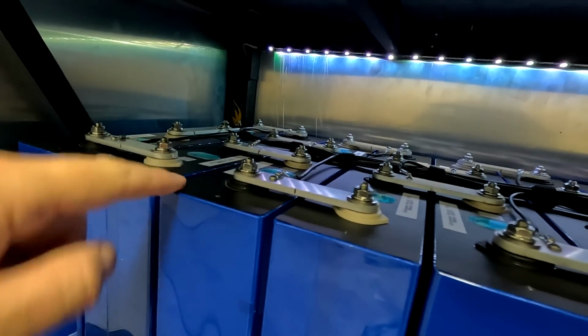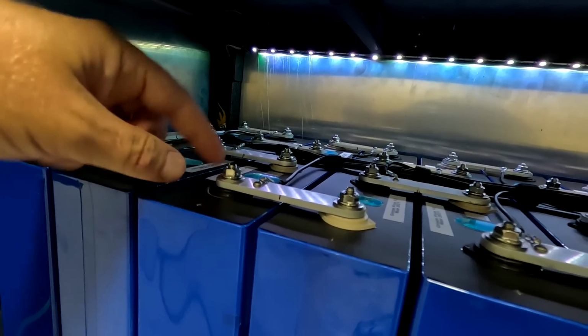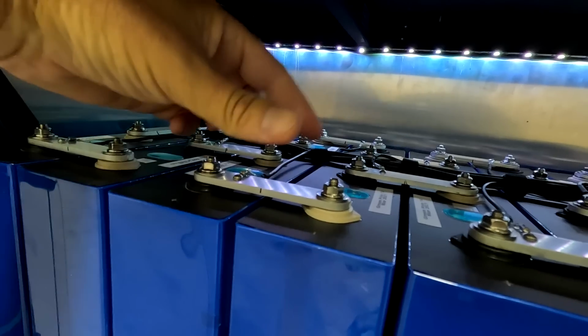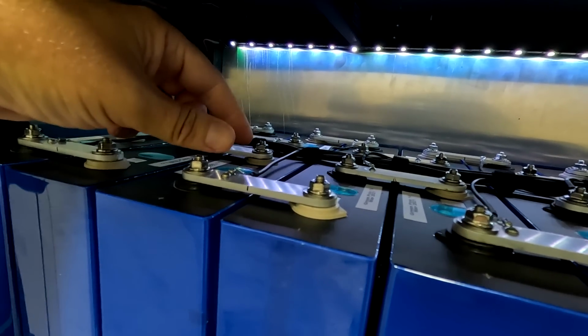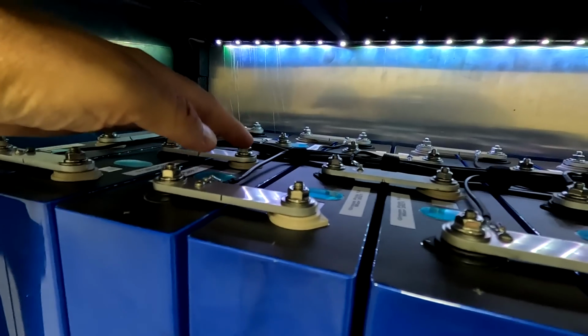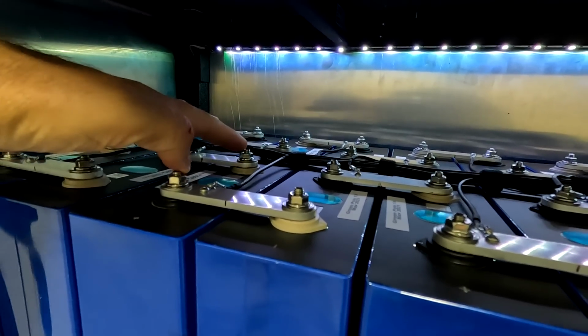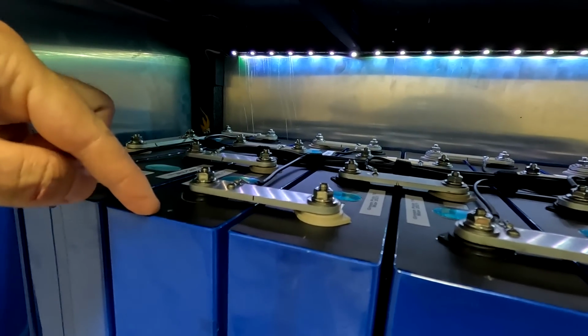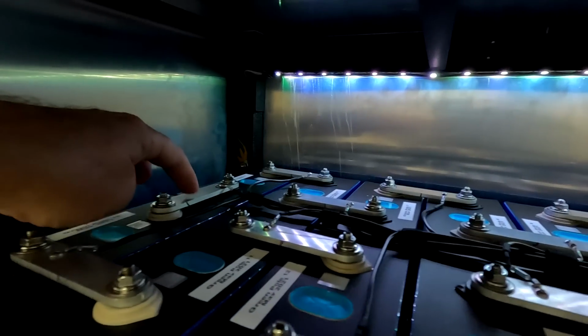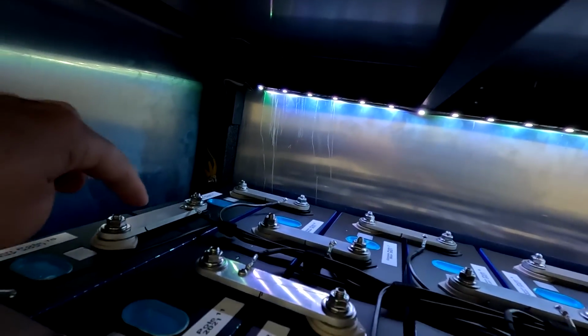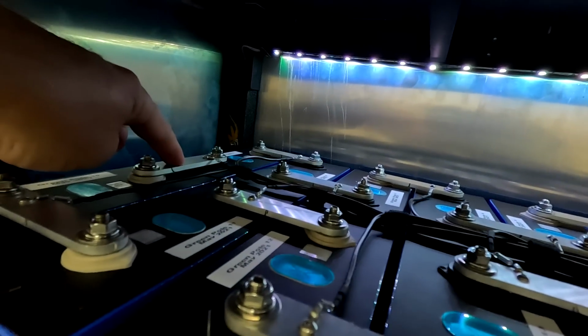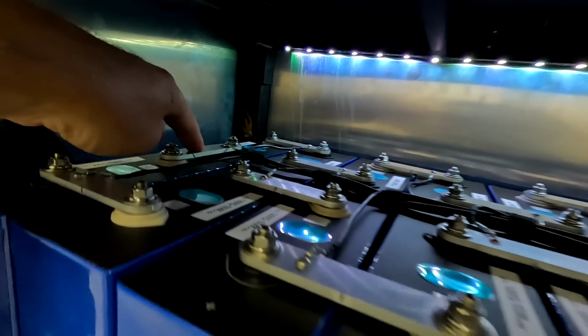With the old batteries, the terminals were further to the middle, while the new ones, the LF280K or the MB30, 31, whatever you're using, have terminals further to the outside of the cell. That's why we need a longer bus bar here. I don't have one in copper, so I'll leave the aluminium bus bar in place for this connection. I won't touch this one, but all the others need to go. We'll start with the most difficult ones on the back.